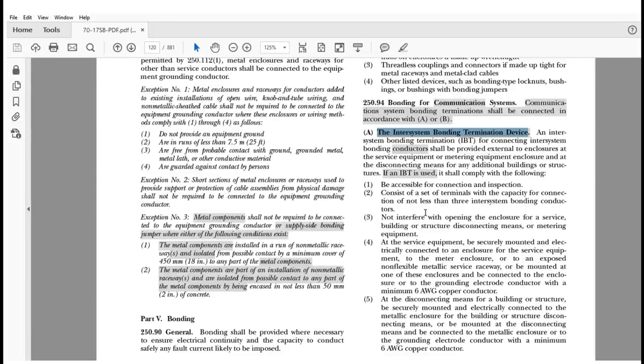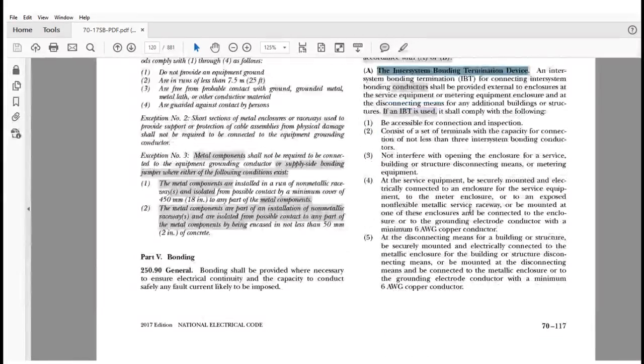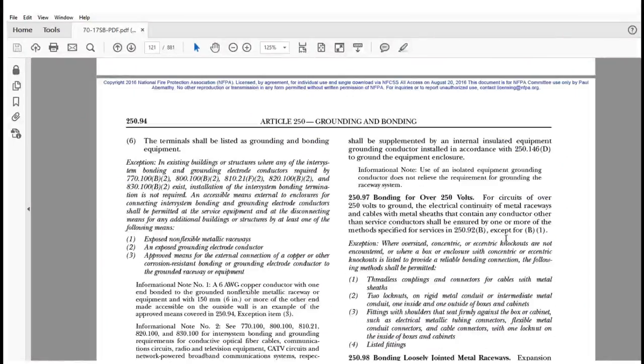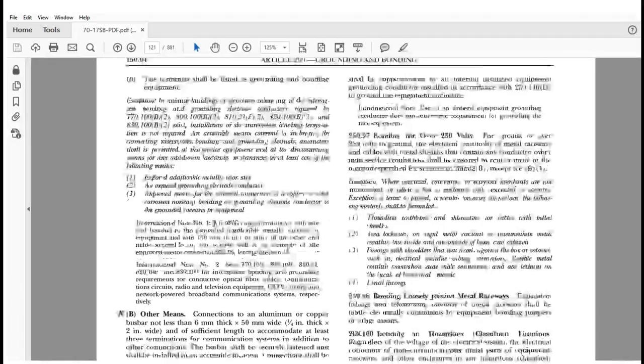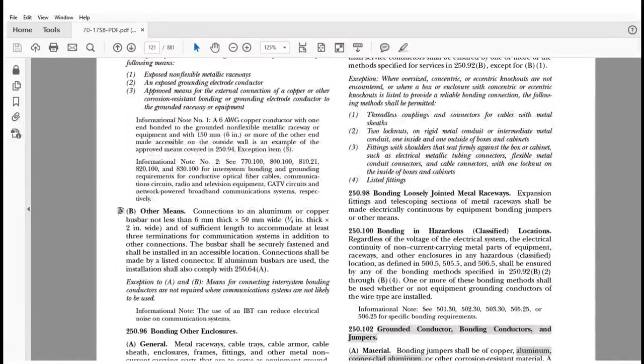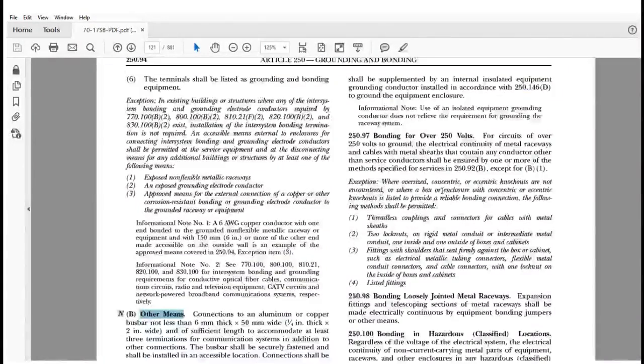Now, if you want to bring other systems to this location, it can't be at this intersystem bonding terminal device that is listed for these communication devices. However, they did add something, you see the N, called other means. So let's say you don't want to do this. You don't want to use that listed device. I'm trying to go back here.